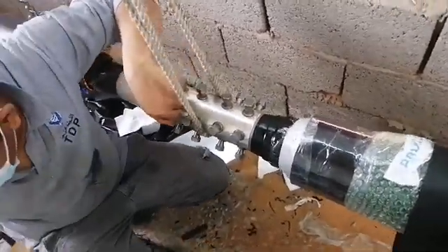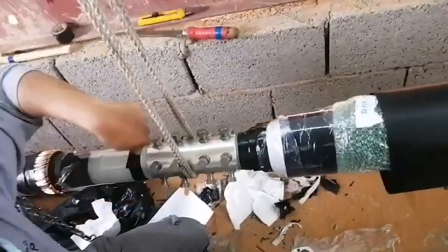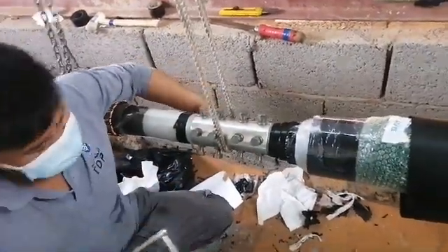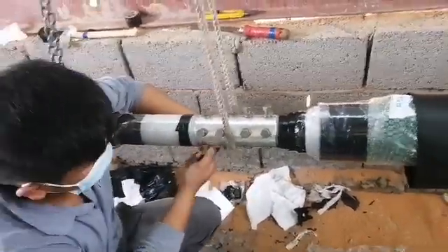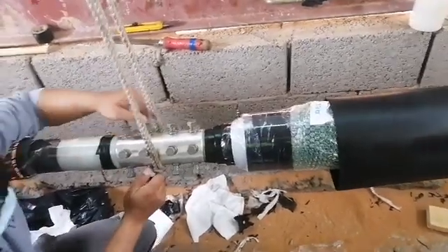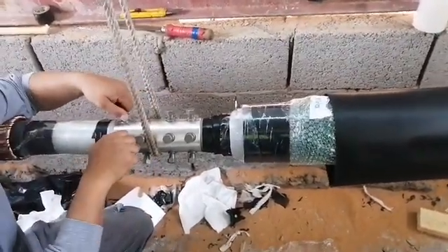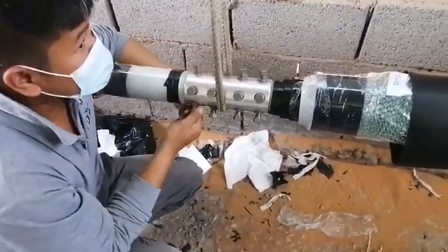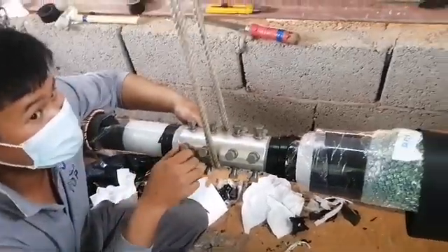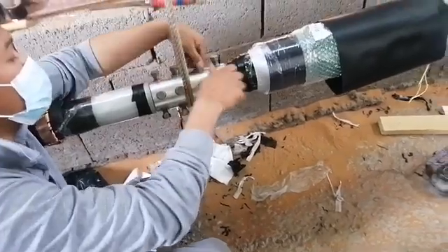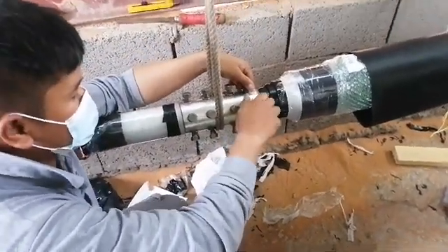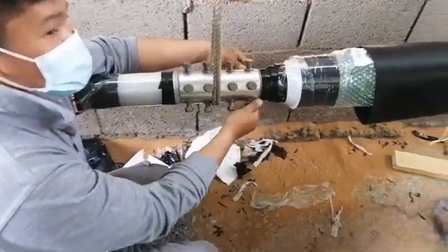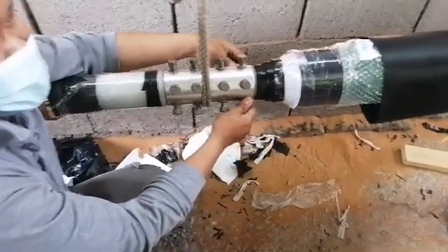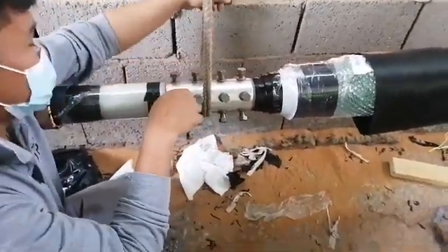After we push the stress cone through the cable, now it's time for jointing. Brugg cable has developed their accessories - before they used the press type, and now the new design is bolted type. The new design is much easier than the press type, because with the press type we needed to use 2 dies.